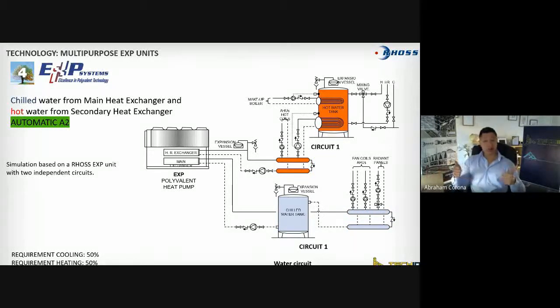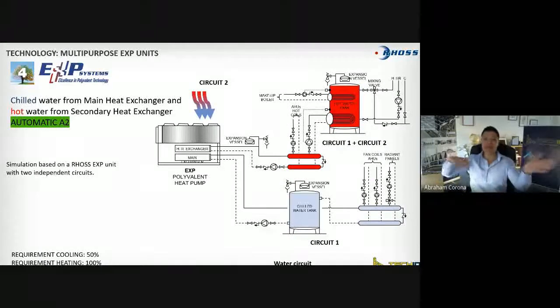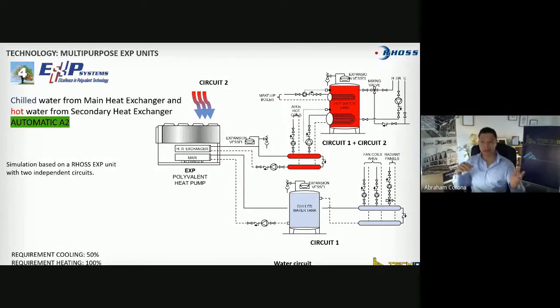Okay, in this case, look, we have shut down one of the circuits completely, and the other circuit is working at 100% of its capacity. That means 50% of cooling, and the other 50% of heating is going to the reuse, and one circuit is down. But here, where is the magic of the EXP by RHOSS? You can even have unbalanced loads or demands of heating and cooling in the same building. So look at that on the left. You have 50% demand of cooling, 100% demand of heating.